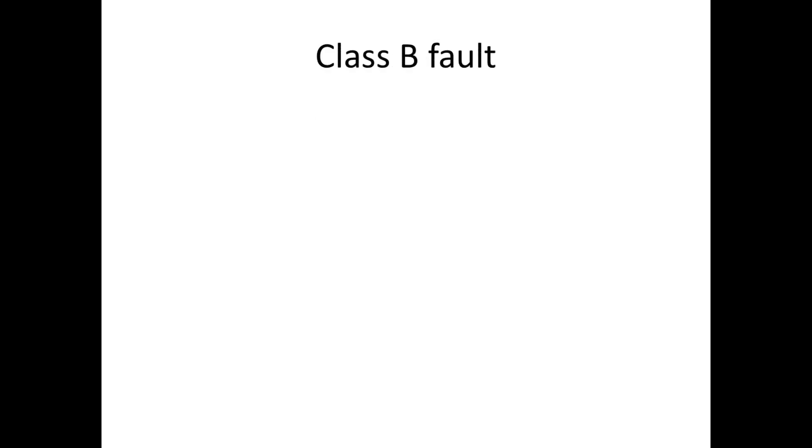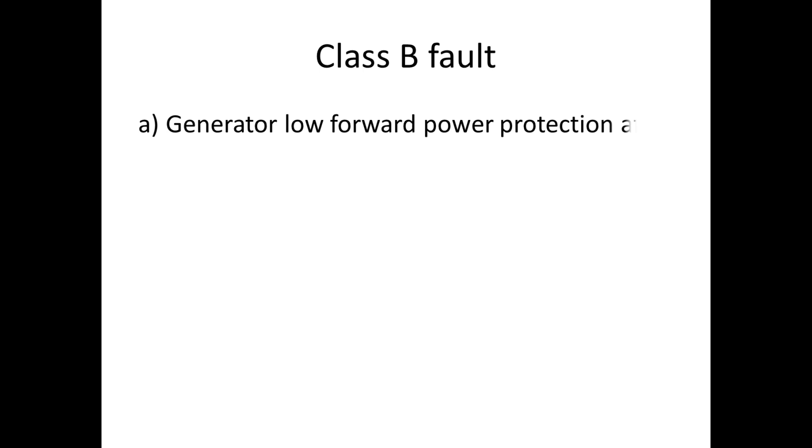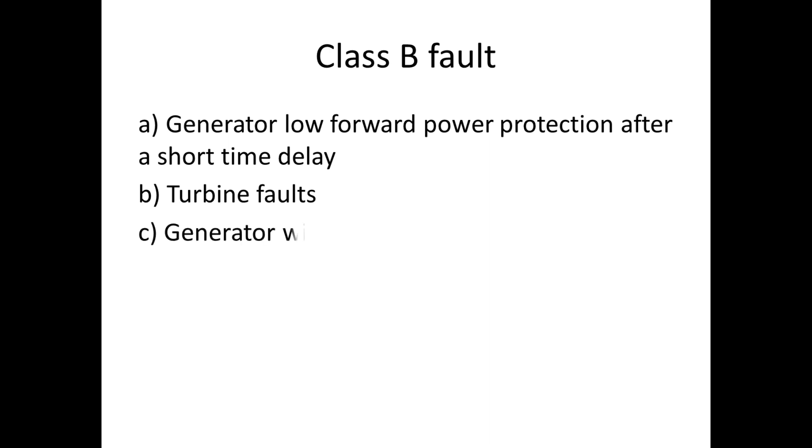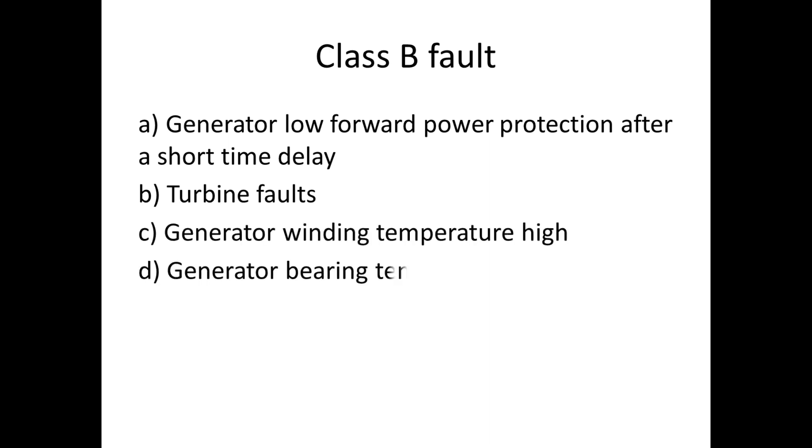I have shown some of the protections which belong to Class B: generator low forward power protection after a short time delay, turbine fault, generator winding temperature high, generator bearing temperature high, and turbine bearing temperature high.